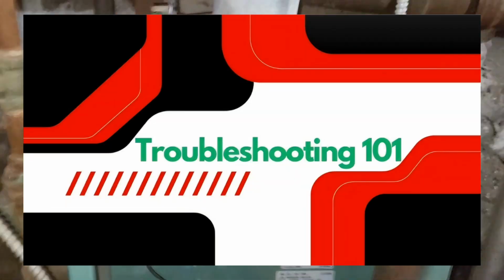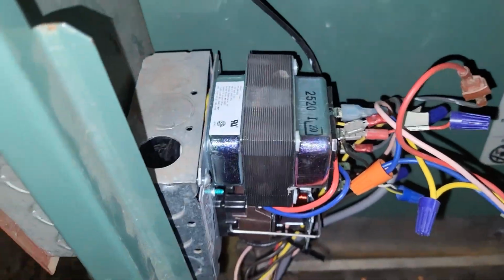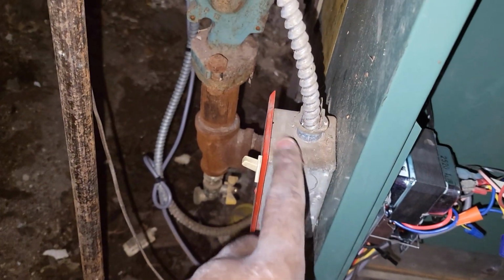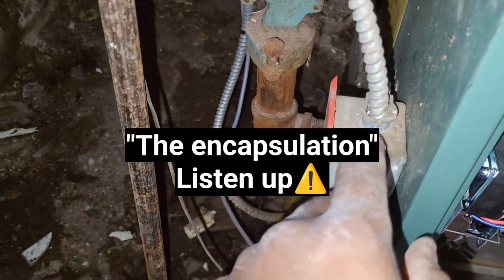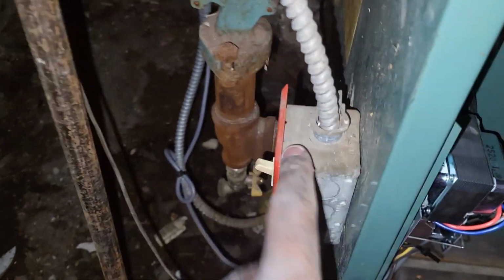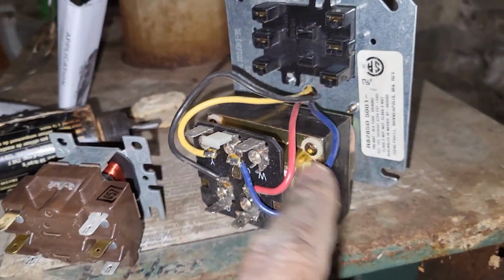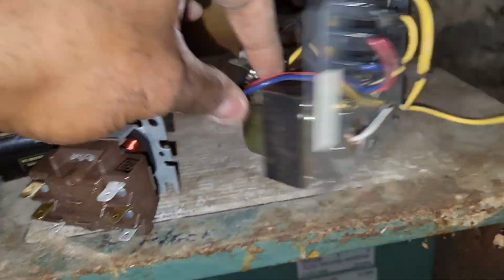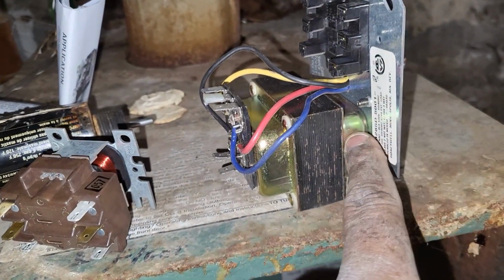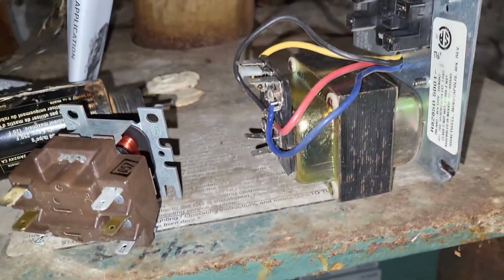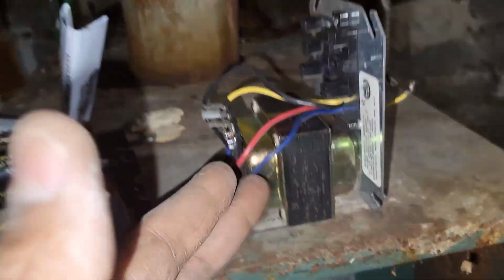What you see here, let me move some stuff out of the way. What you see here is a fan center. We replaced this today, guys. What we found was no power at our L1, L2. We flipped the breakers off and on. Surprisingly, the breakers didn't trip, but we turned the breaker off and on. Once we confirmed we had 115 going to the boiler, we checked for 24. We had no power leaving the transformer. Anytime you got power going to the transformer and nothing coming out, that means you have a bad transformer. That's the effect. You have to figure out what the cause is.